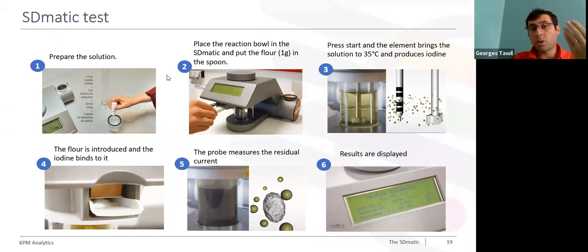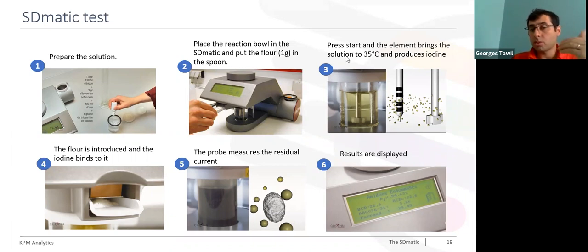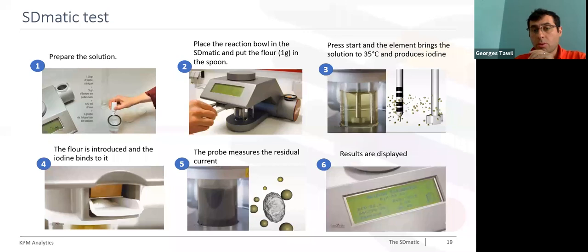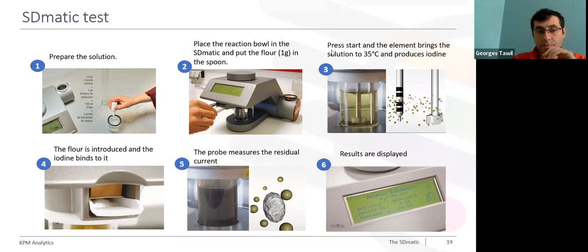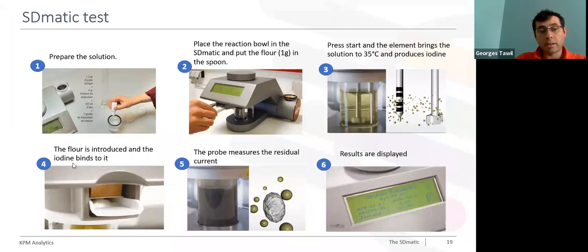Then the operator needs only to place the reaction bowl inside the SD-MATIC and put one gram of flour in the spoon. The third step is to press start, and the SD-MATIC will begin. At this stage, the heating element will bring the solution to 35°C, and at this temperature the machine will start producing iodine. In step four, the flour will be introduced automatically by vibration — the operator doesn't need to do anything — and the iodine will start to bind directly to the flour.